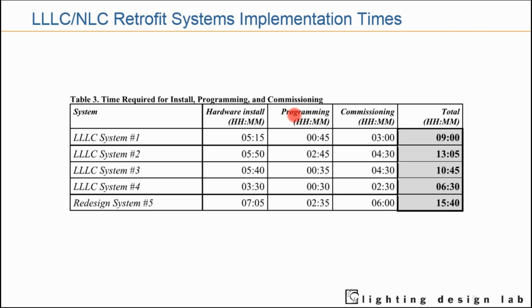Commissioning is not just startup. Startup and programming happen the first time a system comes online, but commissioning is a process that goes on over time and takes many iterations. Until everything is tested, you can't really call it commissioned. You'll also see the total time it took for everything to be implemented.